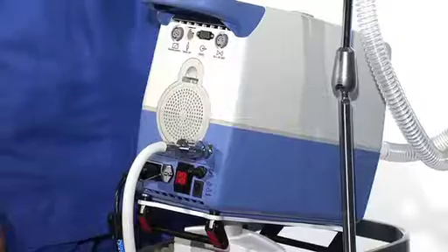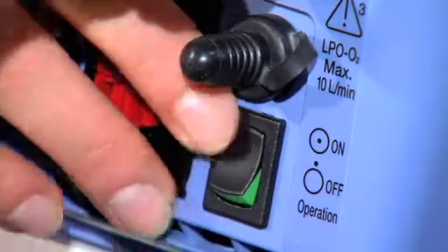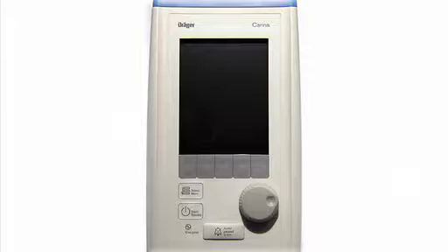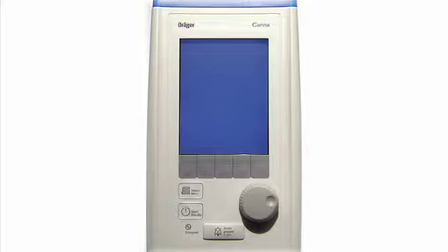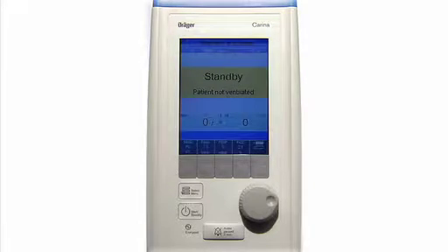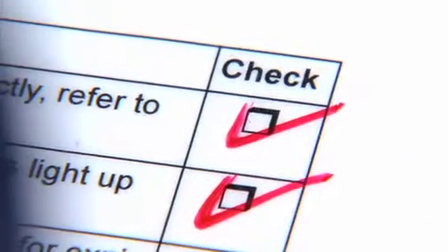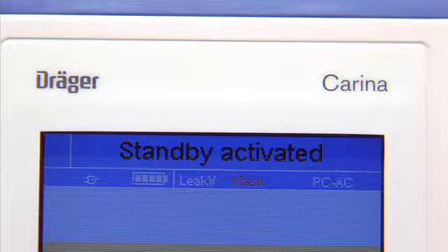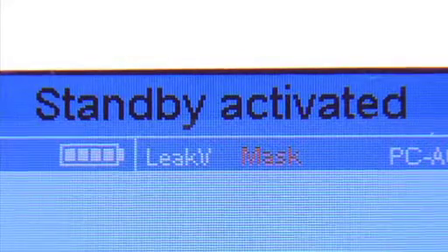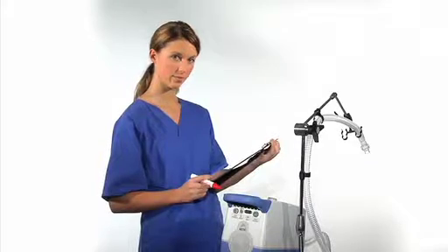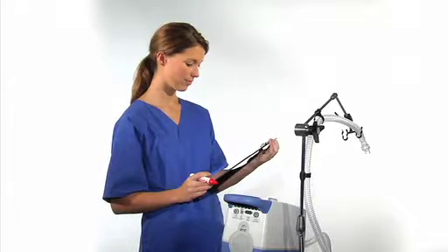To switch Carina on, please push the power switch on the back of the device. When starting up, an alarm will sound briefly and the LEDs will light up. After Carina performs a short internal self-test, the device proceeds to standby mode. The screen provides certain information right away. Please check the status line to verify the correct valve type, leak or expiratory valve, is displayed. If not, change the valve or contact trained personnel to change the selection switch on the bottom of Carina.